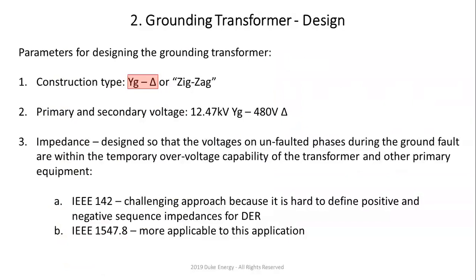Okay. So then you have a choice of primary and secondary voltage, right? 12.47 kV wye-grounded in this case, because it's driven by the primary voltage it's tying into. Secondary can more or less be anything. I have picked 480 volt delta. You can pick anything else you want to. It's, again, an engineer's preference. But note that this grounding transformer does not have any load, so the secondary part of this grounding transformer is not connected to anything, right?